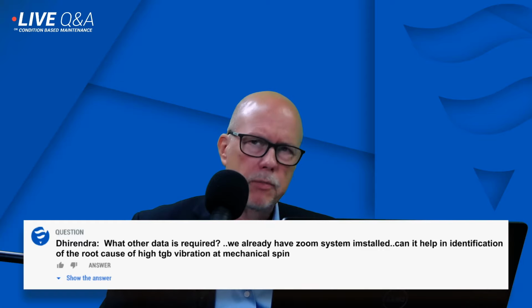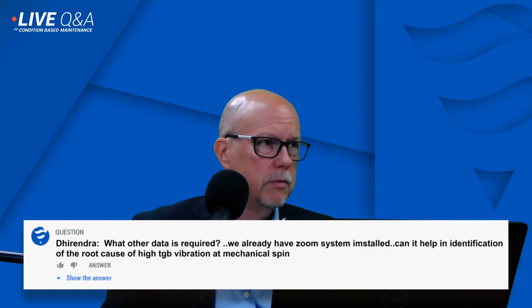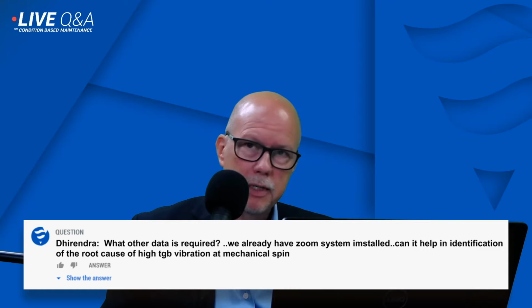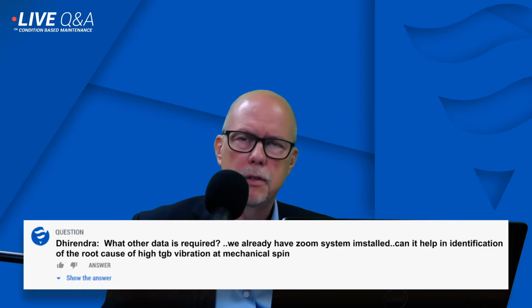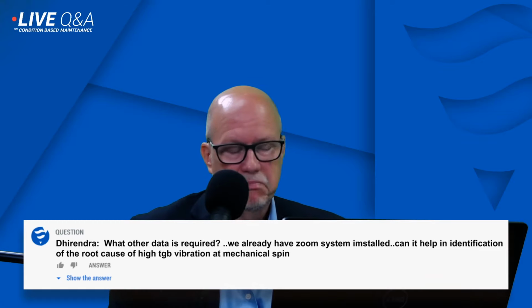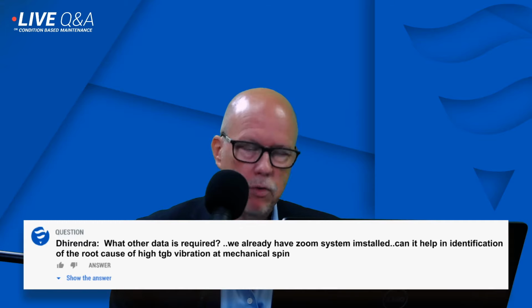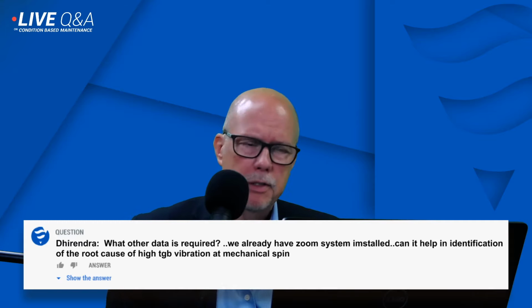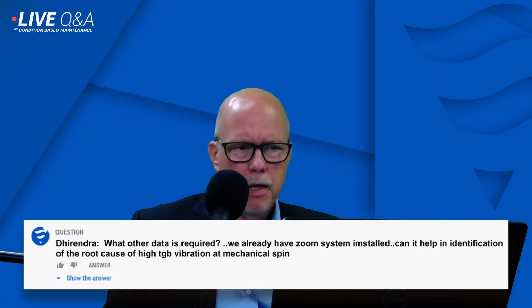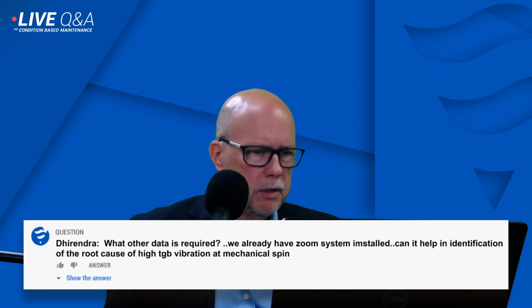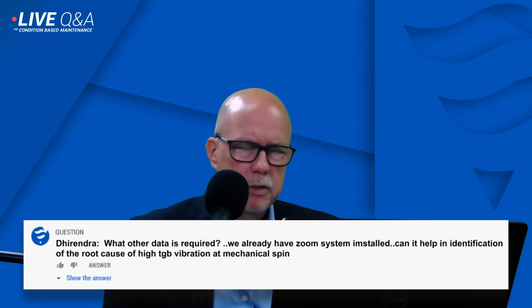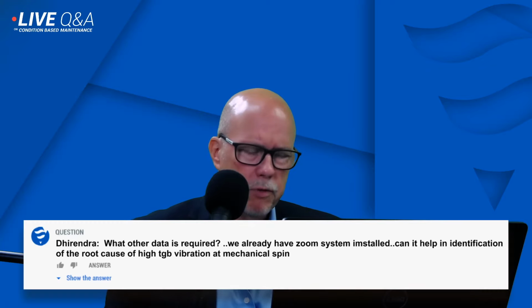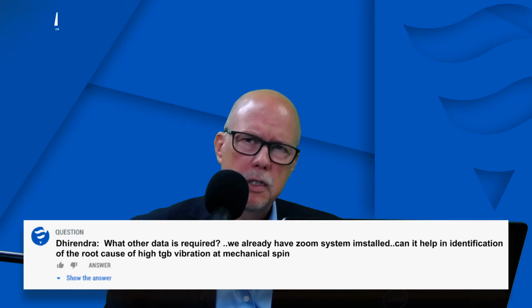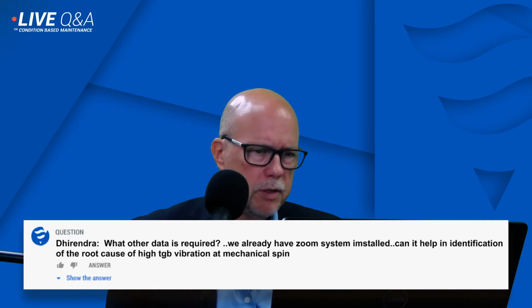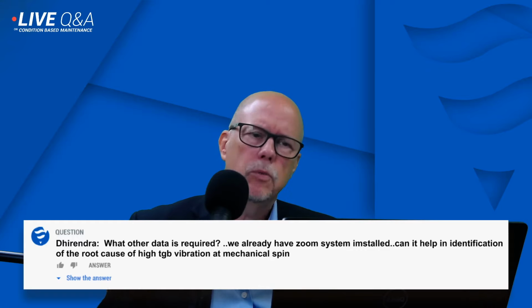Being able to look at the vibration of the turbine from the perspective of frequency. Is it basically at the fundamental frequency, or do we have a series of harmonics? Is it a question of the turbine needing balancing? My instinct is no, because when you operate, it's very low, so you probably don't want to mess with the balancing of the turbine. It might be interesting if you could get in contact with us and maybe we can have a discussion on what you have, because I'm not aware of the project, so we could take a look at what equipment is installed and see how we could find out what the cause of this is.